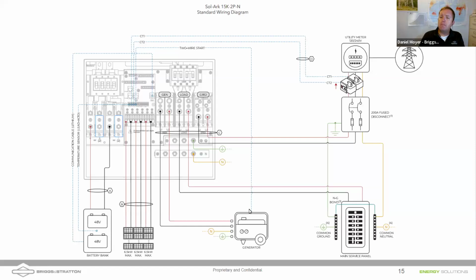One line that's not shown here that I want to address: a lot of generators, including ours, need not only to send power out, but also need to be fed power to keep the starting battery in the generator charged, and for any cold weather kits to keep the battery or block warmers going. Additionally, those wires also let the generator know when grid is or is not present.